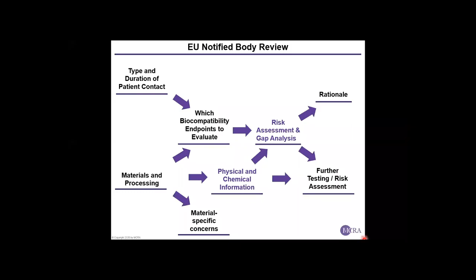There's one other important requirement that's getting a lot of buzz right now. A lot of folks are talking about this, and that is the CMR and ED requirements listed in the regulation of the European MDR. So I've pasted in the exact text here and won't read it word for word, but basically what these requirements mean is, in general, devices need to contain less than 0.1% by weight of any substances which are carcinogenic, mutagenic, toxic to reproduction, or have endocrine disrupting properties.